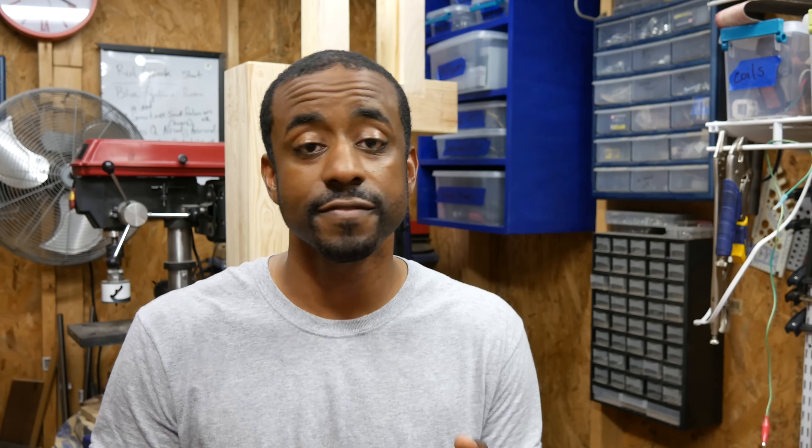There are quite a few questions about three-phase motors — specifically, how to run a three-phase motor on single-phase power. The short answer is: purchase a VFD. Variable frequency drives convert single phase to three phase and will drive your motor; most also have variable speed control. For those who don't want to spend that money and want the absolute cheap option, there is a way to wire a three-phase motor with capacitors to shift the phase on the third line, but there's some risk involved, so I want to make a whole separate video addressing that.